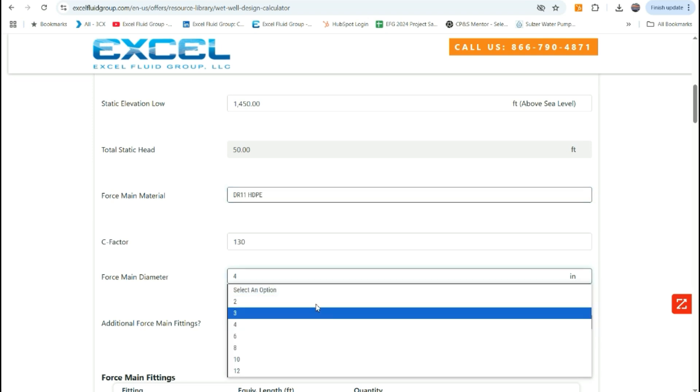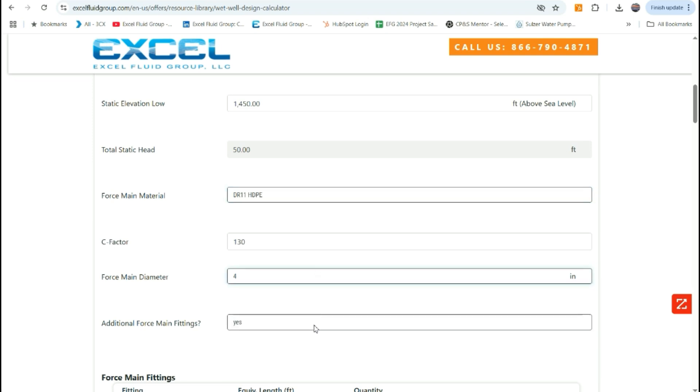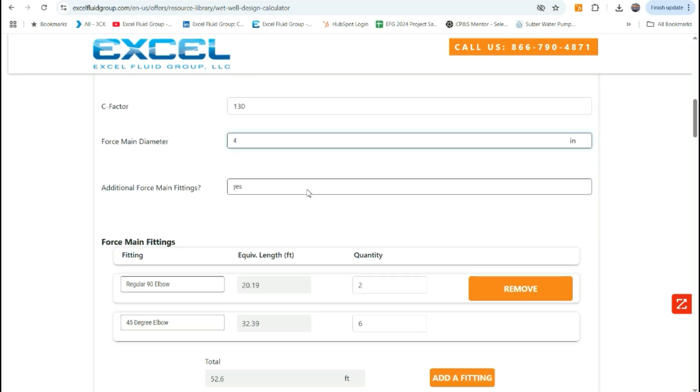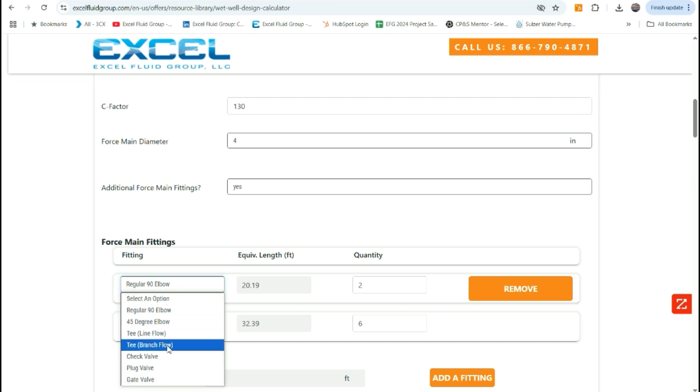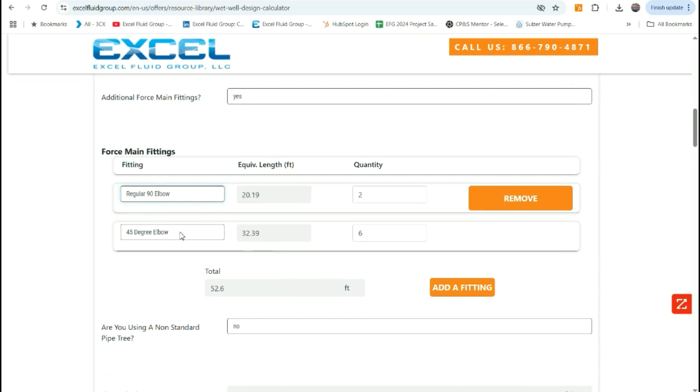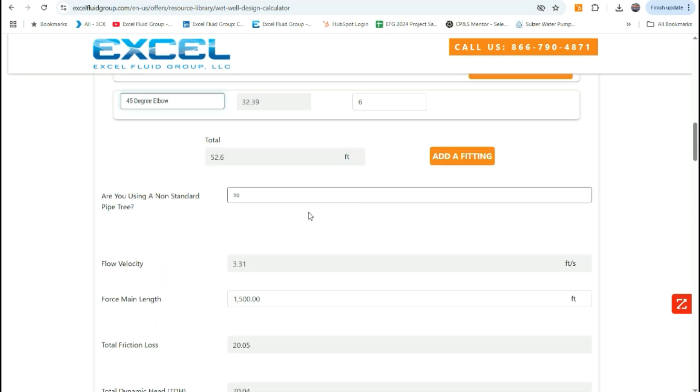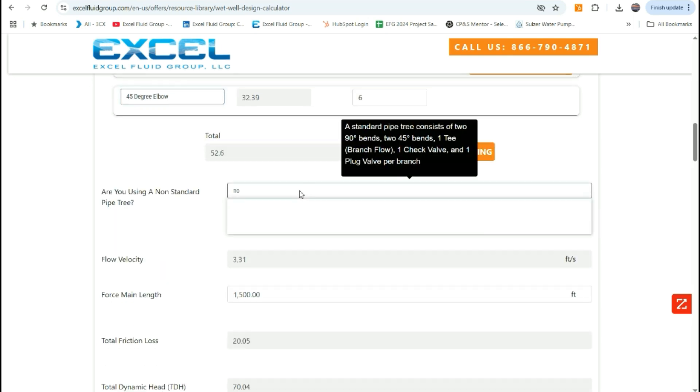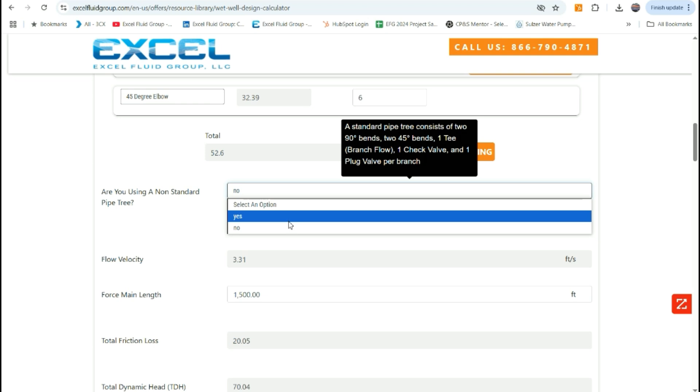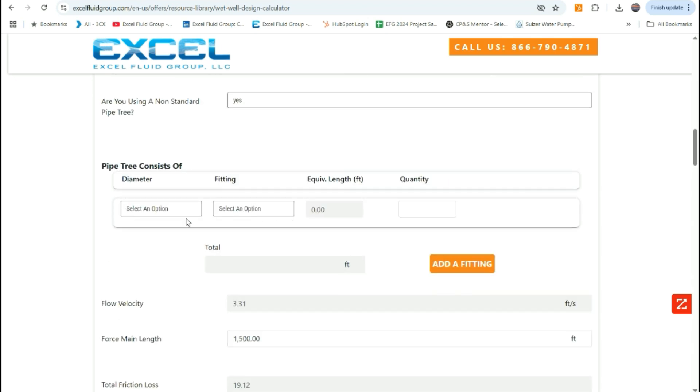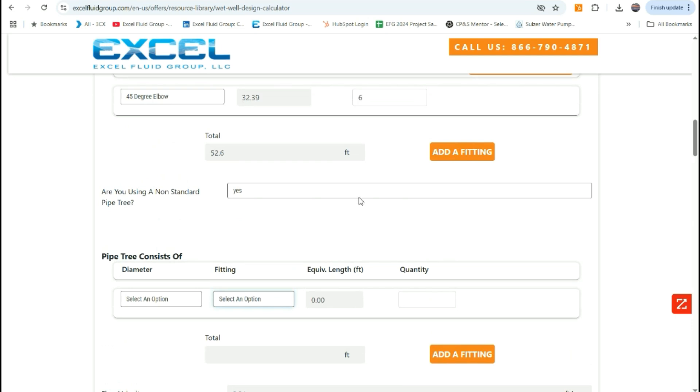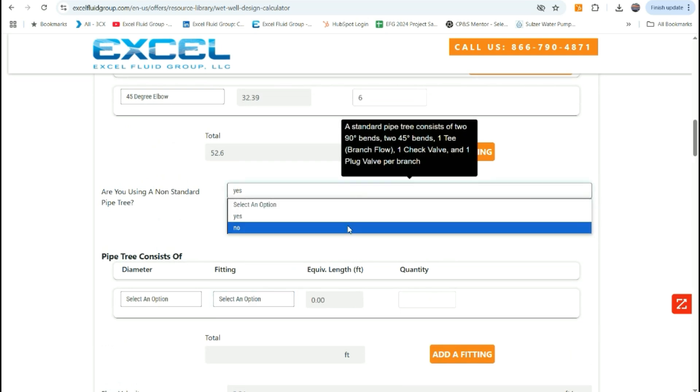There's a few options here. We'll stick with the 4-inch force main, and we can add additional force main fittings by selecting yes here. We can add in a couple of 90s, the equivalent length and the quantities. Elbows or other fittings can be added into the force main calculation. From there, we'll move on to selecting the pipe tree or the pipe and valve tree that would typically be in a valve vault or in above ground enclosure. The standard pipe tree includes two 90s, two 45s, one T, and then a check valve and a plug valve per pump discharge. In this case, we will select no, we are using a standard pipe tree. You can also select yes here and build out a custom pipe tree that is equal or less than the force main diameter.